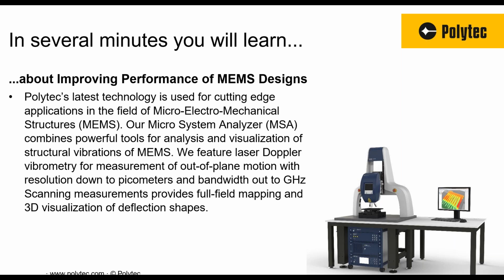Second question here, does laser spot cause a temperature change that can interfere with the measurement? That's a good question. So we're using a 1 milliwatt HeNe laser to do the measurement. So typically that doesn't really heat up the sample.